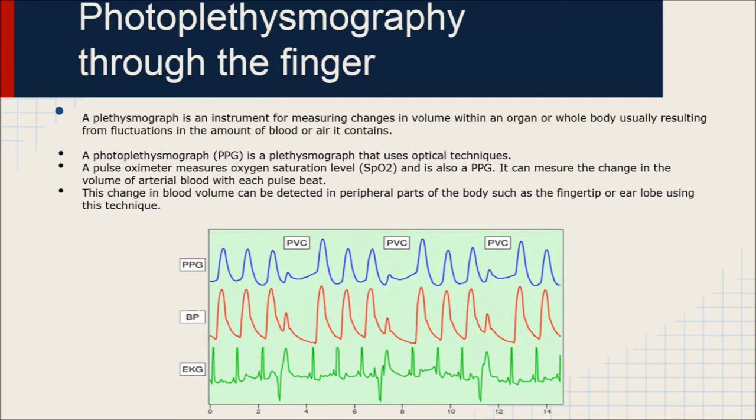A photoplethysmograph is a plethysmograph that uses optical techniques. A pulse oximeter measures oxygen saturation levels and is also a PPG. It can measure the change in the volume of arterial blood with each pulse beat. This change in blood volume can be detected in peripheral parts of the body such as the fingertips or earlobes using this technique.